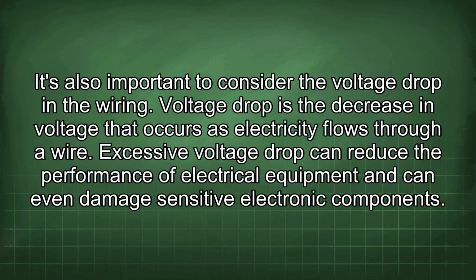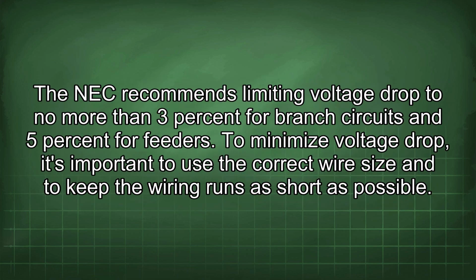It's also important to consider the voltage drop in the wiring. Voltage drop is the decrease in voltage that occurs as electricity flows through a wire. Excessive voltage drop can reduce the performance of electrical equipment and can even damage sensitive electronic components. The NEC recommends limiting voltage drop to no more than 3% for branch circuits and 5% for feeders. To minimize voltage drop, it's important to use the correct wire size and to keep the wiring runs as short as possible.